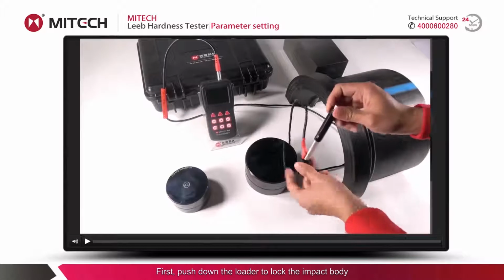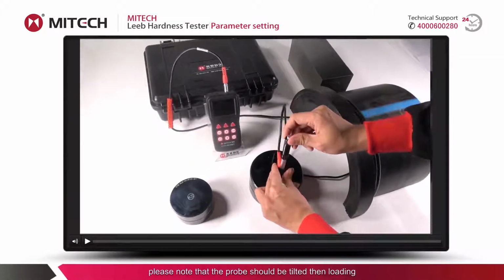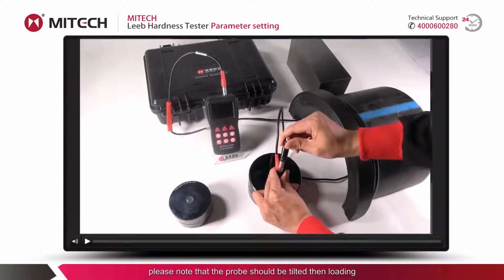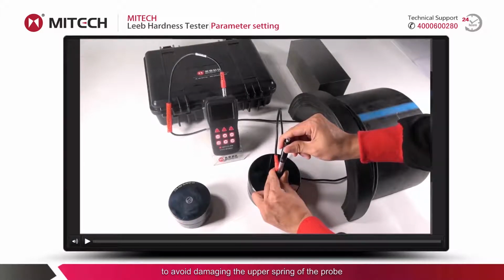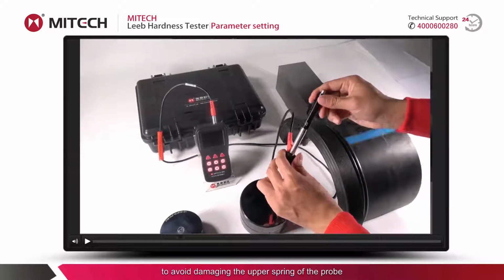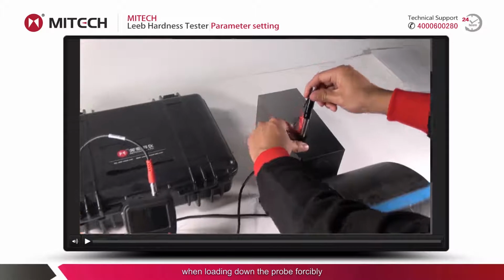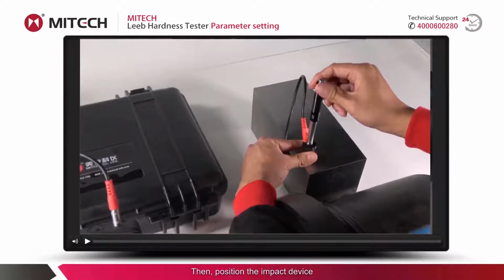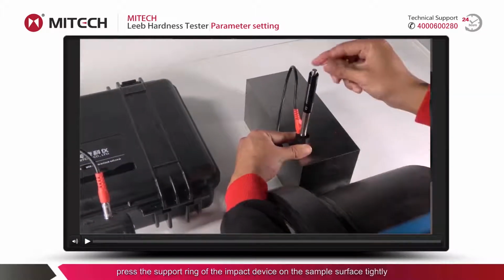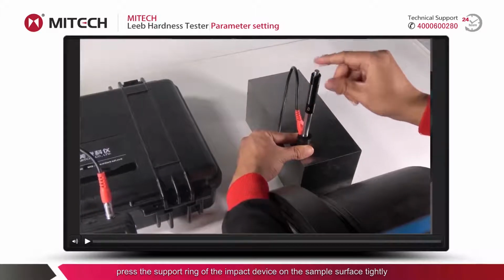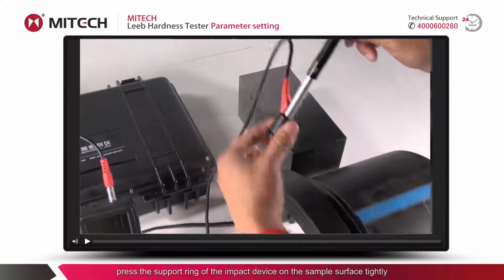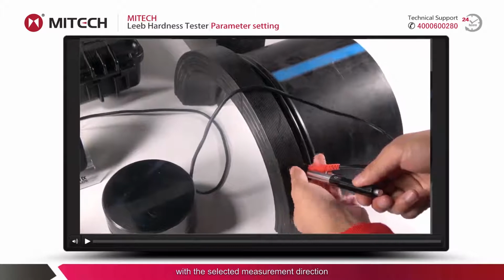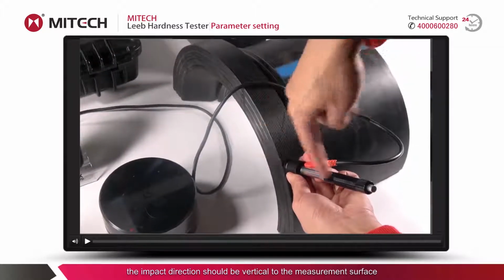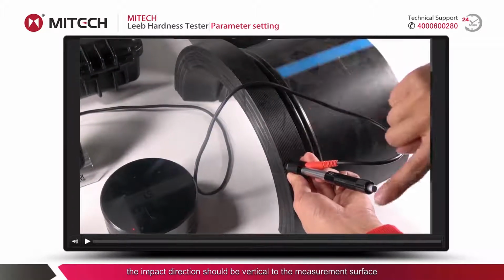First, push down the loader to lock the impact body. Please note that the probe should be tilted, then loaded, to avoid damaging the upper spring of the probe when loading down the probe forcibly. Then position the impact device. Press the support ring of the impact device on the sample surface tightly. With the selected measurement direction, the impact direction should be vertical to the measurement surface.